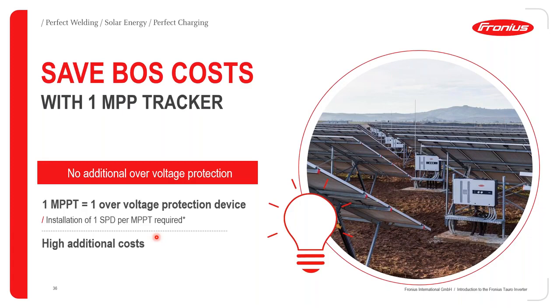Therefore, an inverter with additional MPPTs will have additional costs for SPDs, because each MPPT channel has to be protected accordingly. So we look at the Tauro Eco version of the commercial inverter as optimizing the BOS cost as far as the SPDs are concerned, because you only require one set for the one MPPT that is included.